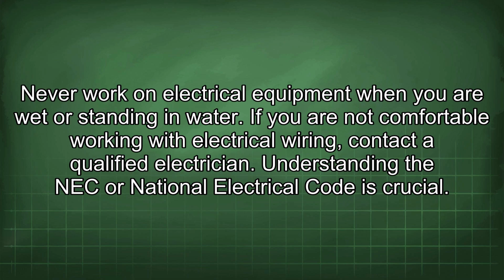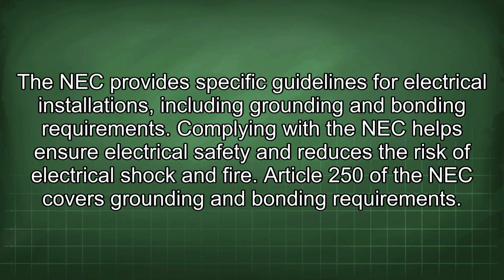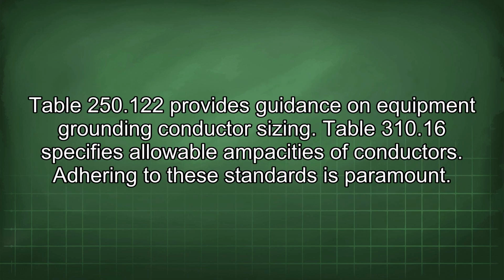Understanding the NEC, or National Electrical Code, is crucial. The NEC provides specific guidelines for electrical installations, including grounding and bonding requirements. Complying with the NEC helps ensure electrical safety and reduces the risk of electrical shock and fire. Article 250 of the NEC covers grounding and bonding requirements. Table 250.122 provides guidance on equipment grounding conductor sizing. Table 310.16 specifies allowable ampacities of conductors. Adhering to these standards is paramount.